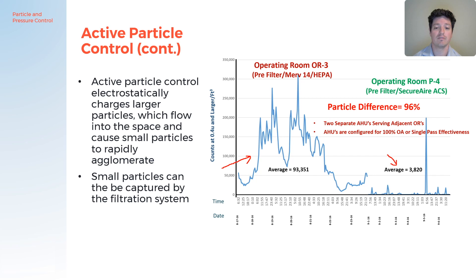Active particle control is suitable for new construction and retrofits alike. It has a low pressure drop, so you typically don't need to upgrade fans, and it can replace a standard MERV 14 filter bank within the air handling system or ductwork. At only nine inches of depth versus up to 12 inches for a typical MERV 14 filter, it can be a direct replacement for that system.